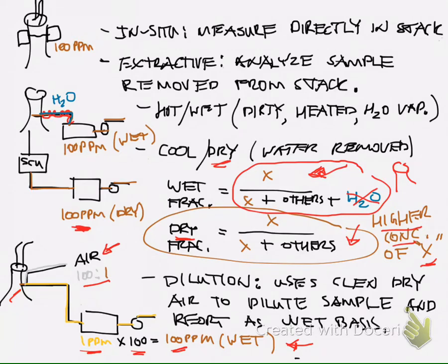Whereas in the dry method over there, we had to indicate that it was dry, because that's going to tell us that the concentration is actually higher, and we'd have to apply a factor, which is this dry factor right here. We'd have to apply a factor to the measurement to get the correct value in the stack. So hopefully that all makes sense there.